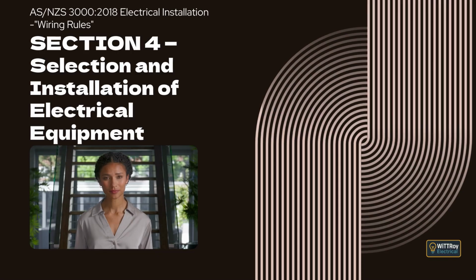Clause 4.4.1.2 Different systems. This clause explains that where extra low voltage and higher voltage systems exist in the same premises, any socket outlet supplied at extra low voltage must be clearly marked with their voltage and be designed so that an extra low voltage plug cannot be inserted into a socket outlet connected to a higher voltage system. It also explains that socket outlets for SELV and PELV systems must not have an earthing contact and must comply with the relevant clause referenced in this section.